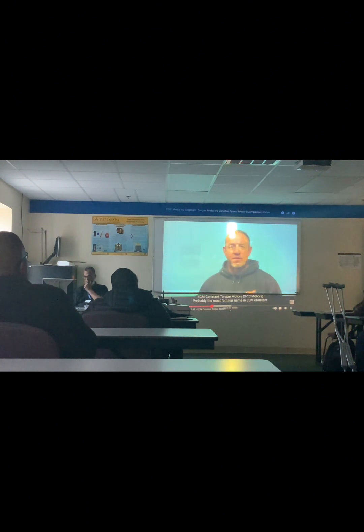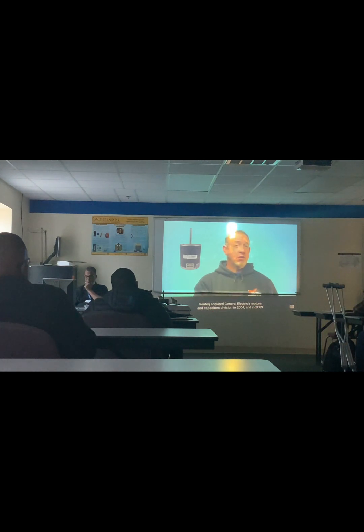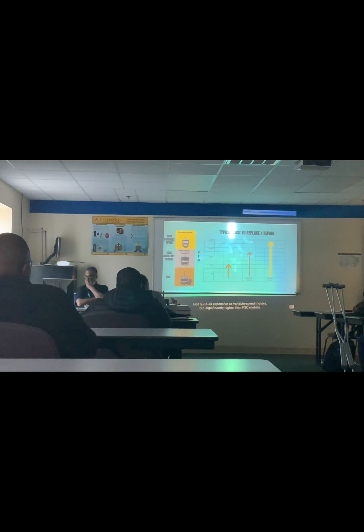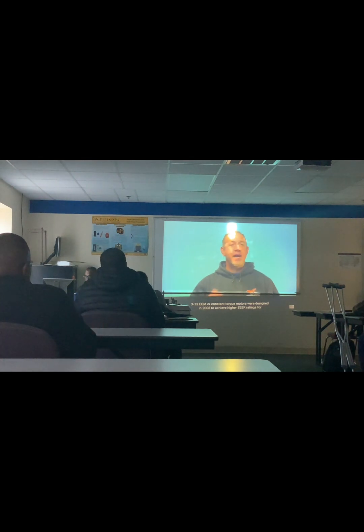ECM constant torque motors. Probably the most familiar name in ECM constant torque motors is the X13 motor by Genteq. Genteq acquired General Electric's Motors and Capacitors division in 2004, and in 2009 renamed themselves Genteq. I bring this up because the first high-efficiency residential HVAC ECM motors were made by GE back in the 1980s. Even though they're like upgraded PSC motors, they're a little bit more complicated in design because they use an integrated control board to send the signal for operation and at what speed or torque setting to run at. Because of this, they're more expensive. Not quite as expensive as variable speed motors, but significantly higher than PSC motors. X13 motors were designed in 2006 to achieve higher SEER ratings for the air conditioners being put into homes. The government set the standard. What does SEER mean? SEER rating, what is that?